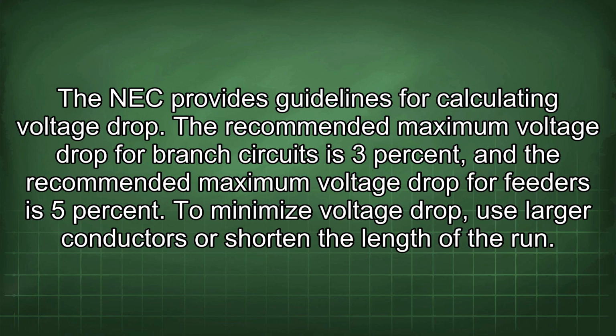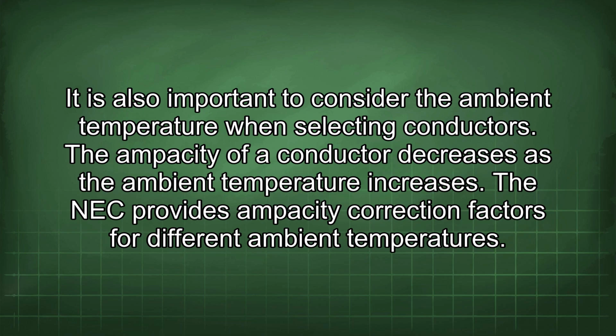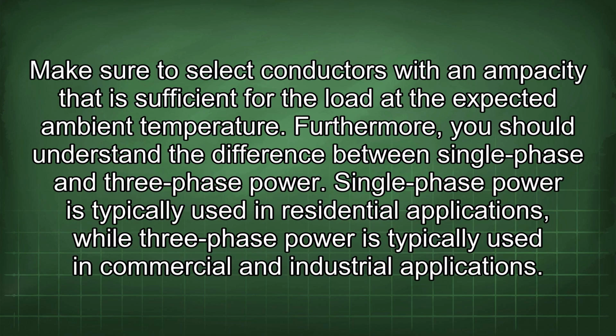The recommended maximum voltage drop for branch circuits is 3%, and the recommended maximum voltage drop for feeders is 5%. To minimize voltage drop, use larger conductors or shorten the length of the run. It is also important to consider the ambient temperature when selecting conductors. The ampacity of a conductor decreases as the ambient temperature increases. The NEC provides ampacity correction factors for different ambient temperatures. Make sure to select conductors with an ampacity that is sufficient for the load at the expected ambient temperature.